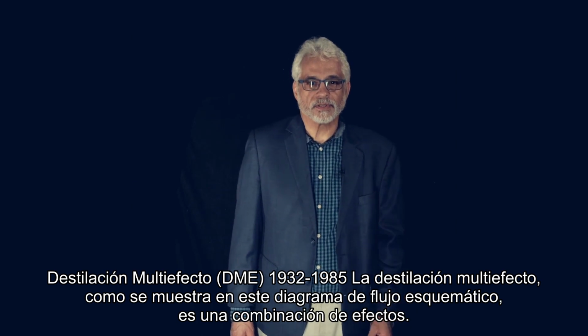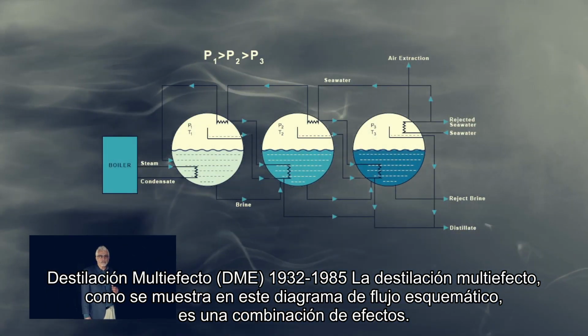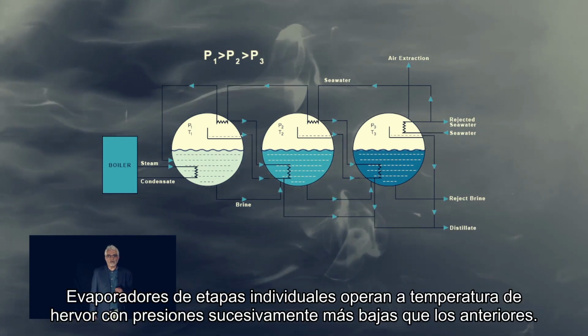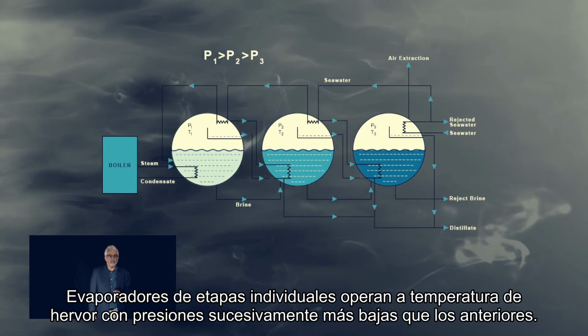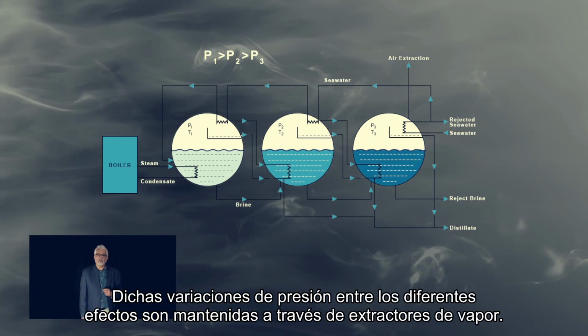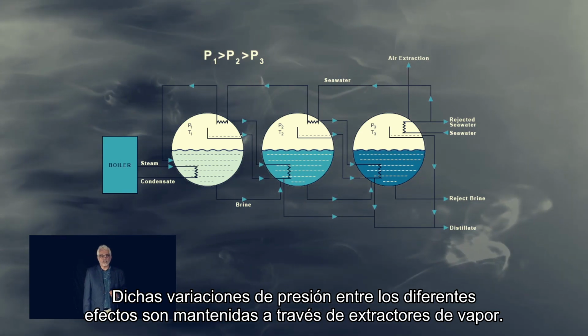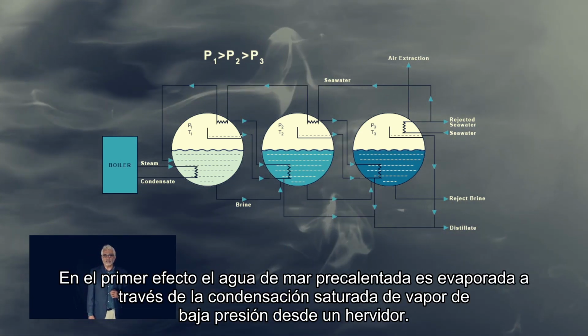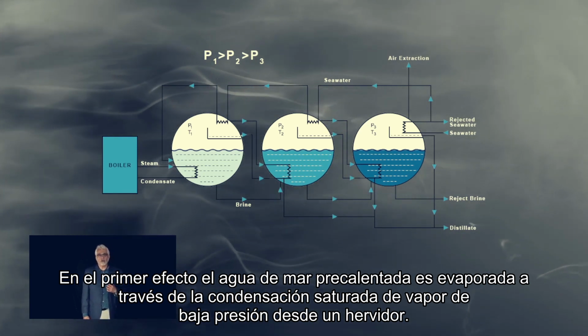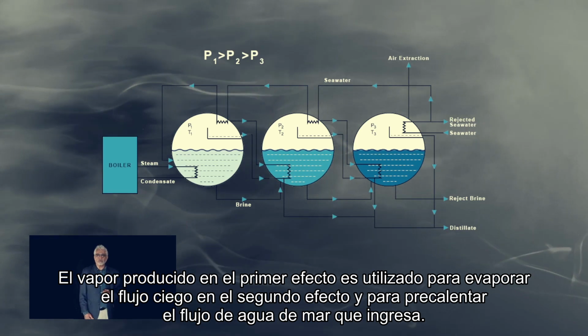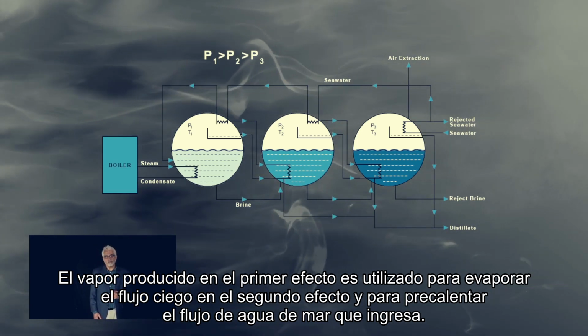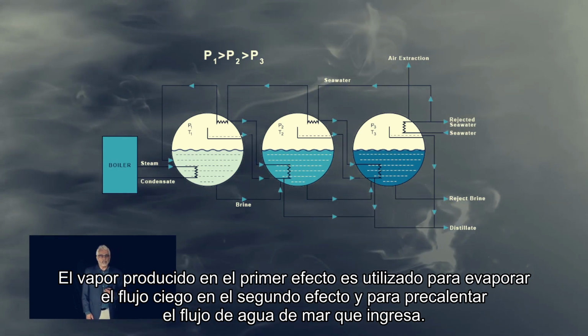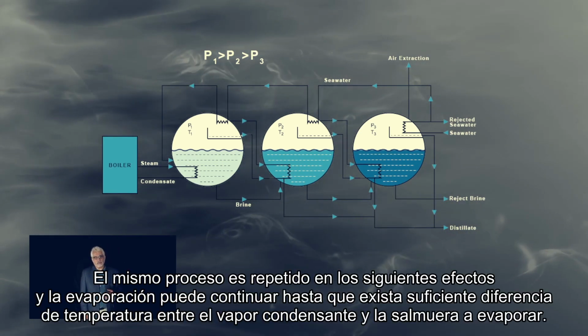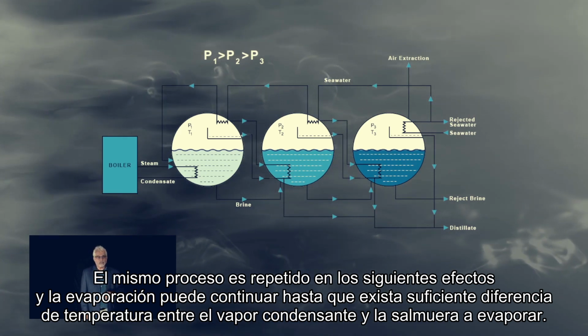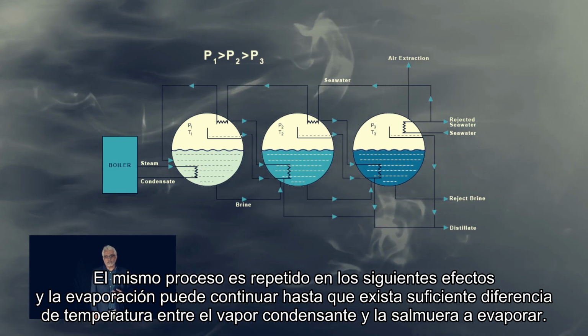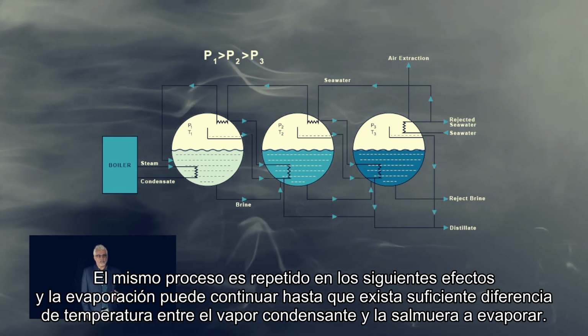The multi-effect distillation process, as shown in the schematic flow diagram, is a combination of effects: single-stage evaporators operating at successively lower pressure and boiling temperature than the preceding ones. The pressure difference in the effects is maintained by steam ejectors. In the first effect, the preheated seawater is evaporated by condensing saturated low-pressure steam from a boiler. The produced vapor in the first effect is used to evaporate the brine flow in the second effect and to preheat the incoming seawater feed. The same process is repeated in the following effects, and evaporation can continue until there is enough temperature difference between the condensing vapor and the evaporating brine.